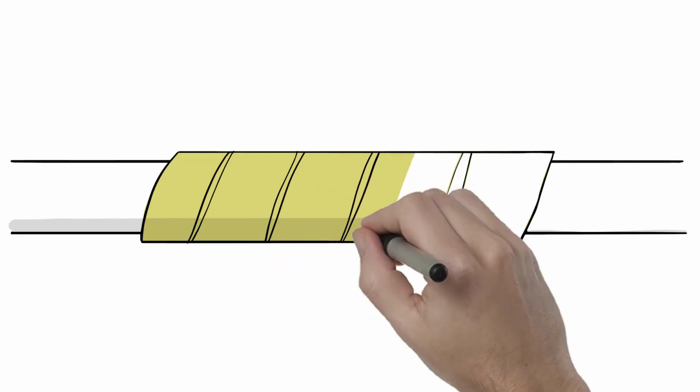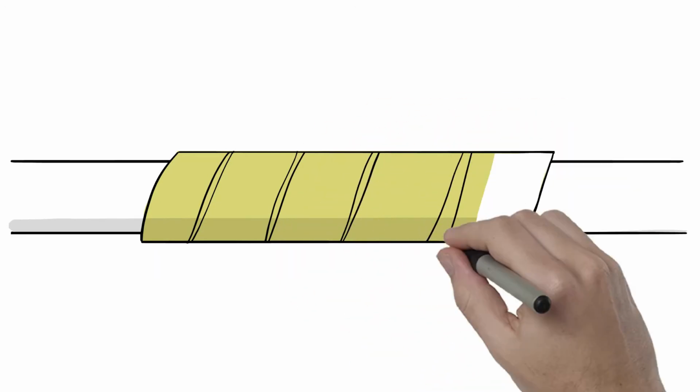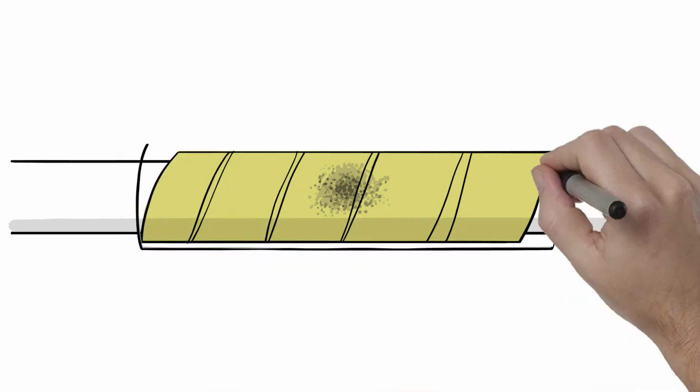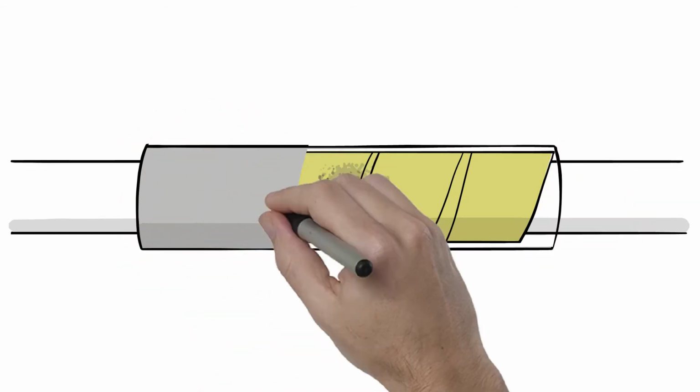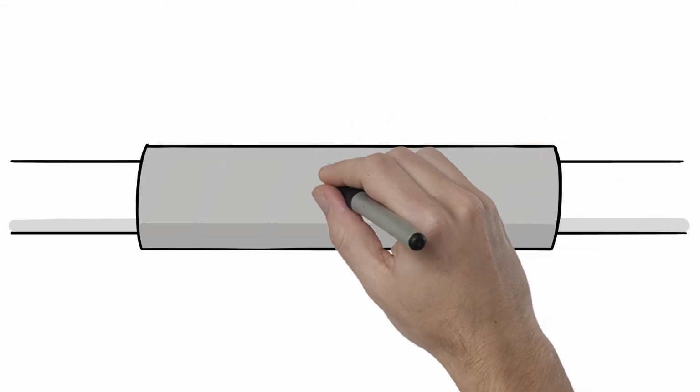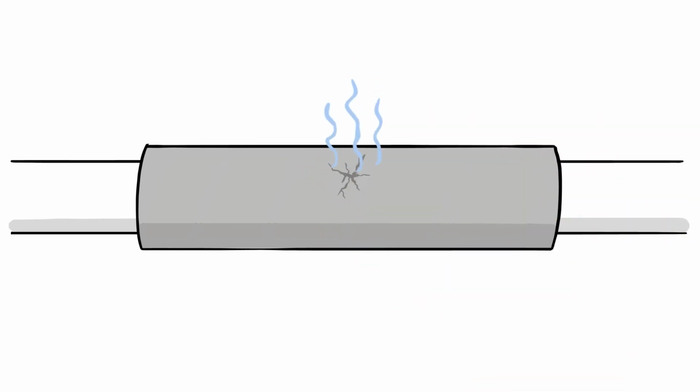If you add thick enough insulation to the outside of the pipe, you'll bring the surface temperature above the dew point, preventing condensation. But if you use fiberglass insulation, water vapor may still pass through the insulation, reaching the pipe surface and condensing there. Then it just sits there, getting moldy or corroding the pipes. That's why fiberglass insulation needs an extra vapor barrier or jacket to prevent moisture from passing through the fiberglass insulation. But even a nick in the jacket could allow that water to get in.